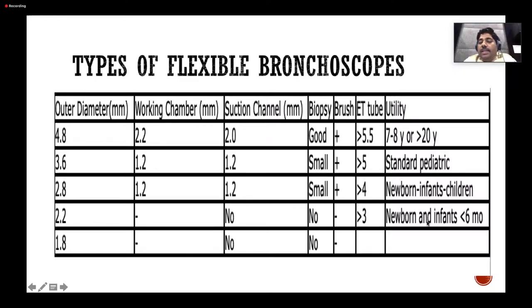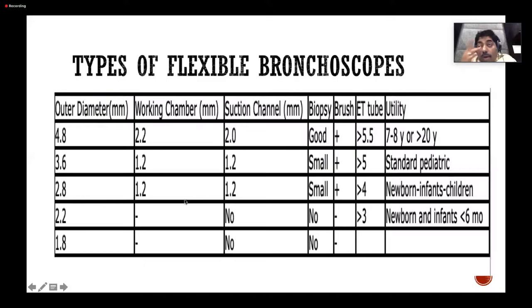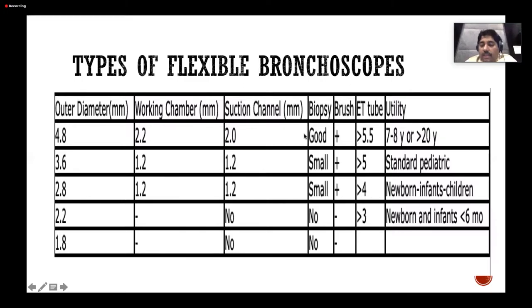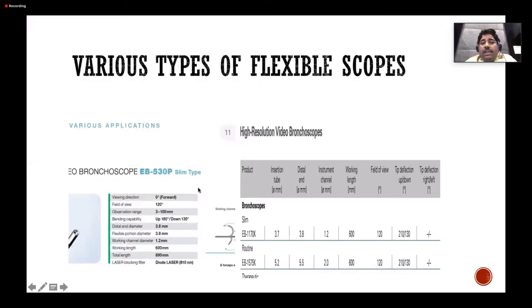The 2.2 mm Olympus ultra-thin scope has no suction channel and no biopsy forceps capability — it is used in newborns and infants. For a preterm child intubated with a 3.5 size tube, a 2.2 or 2.8 mm scope can be used, though you have only a 0.7 mm gap for aeration. The 4 mm Olympus scope has a 2 mm suction channel.